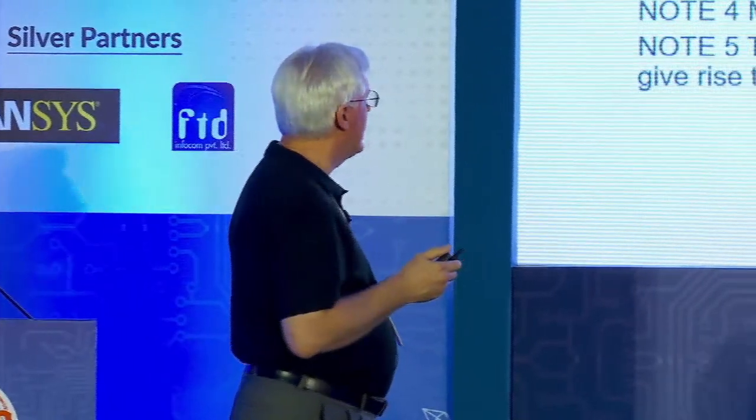So this is a clause that was actually added to the standard in 2016, and what it specifically said is that you need to do some kind of a cyber assessment on your system. And you notice there about in the middle of the page towards the bottom, in the notes of the 61508 standard, it specifically mentions 62443 as the primary source for doing your cyber risk assessment.